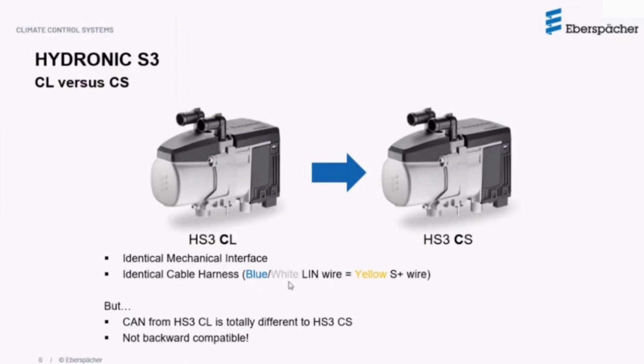But because there's no longer 2 different harnesses, the same harness with the yellow wire is still used for the CL version. You have to keep in mind that when you install a CL version heater and you're using an Easy Start Timer, on the timer side it still remains blue-white, but that blue-white now will connect to the yellow on the main harness. This is an important note that you must keep in mind.